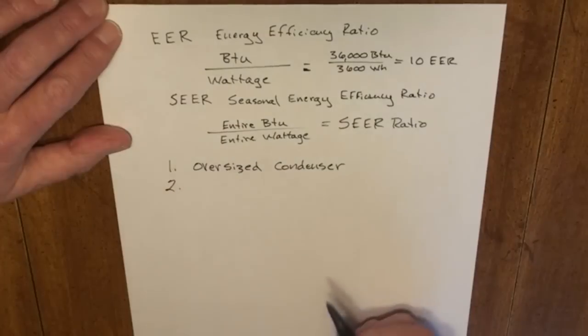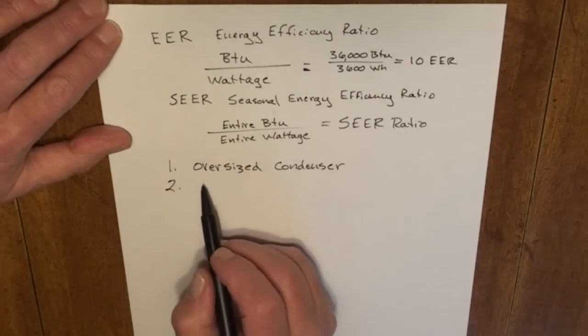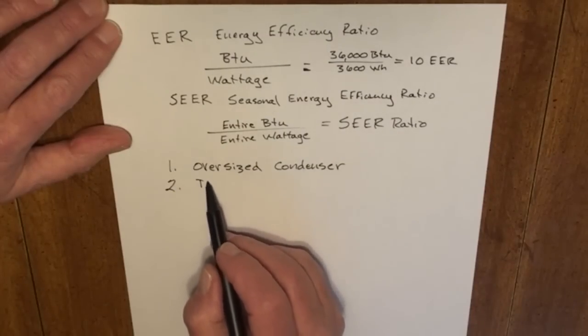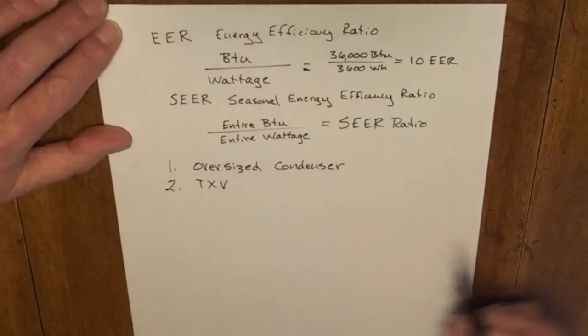The second most popular addition would be the thermostatic expansion valve. The TXV allows the refrigerant superheat in the evaporator to remain constant, even during load changes. Let's say the house is hot and we're doing a hot pull down on the house.